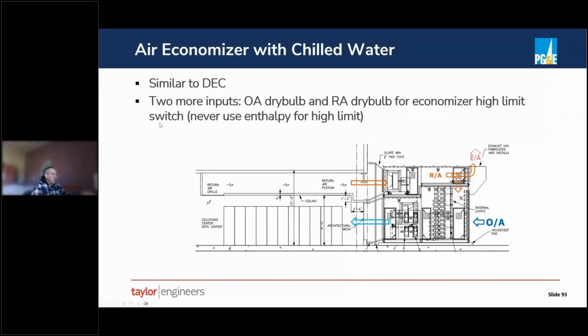And so now you do need to know if your return air is hotter than your outside air, you want to shut off your economizer. One word of advice there is never use enthalpy as a way to control an economizer. It's actually not even allowed by code in California anymore. And the main reason is that enthalpy sensors or humidity sensors are hard to calibrate and often get bad information. Whereas dry bulb is generally much easier to accurately measure and therefore not do the wrong thing in terms of enabling or disabling your economizer. So we only use dry bulb to enable and disable economizer.